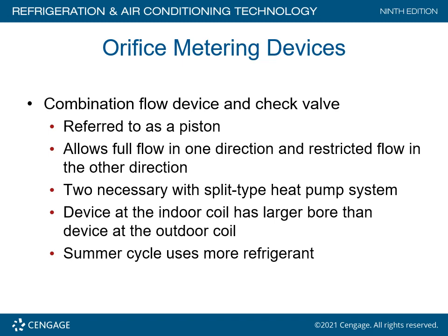So typically, as a rule of thumb, and that's all this is, you're going to utilize about 65, maybe 70% of the refrigerant charge in the heating mode. Whereas in the cooling mode, you're going to use 100% of that refrigerant.